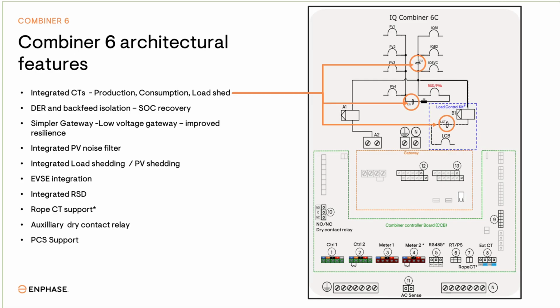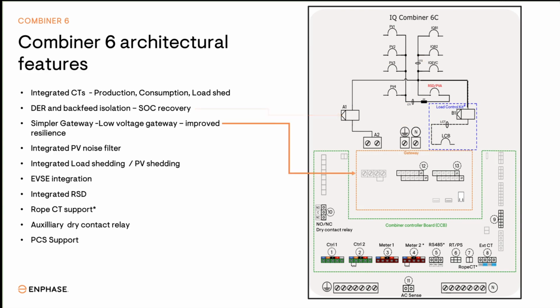Connected PV systems that can't be directly controlled by the Enphase IQ gateway can be shed through the load control port. The integrated load control CT can be reconfigured to measure PV production in these use cases. Another feature is the simplification of the IQ gateway from a line voltage gateway to a low voltage DC gateway. The DC-powered gateway is more resilient to power fluctuations caused by line-level voltage changes and can be supported and powered by low voltage power from the Combiner 6C and the Battery 10C.